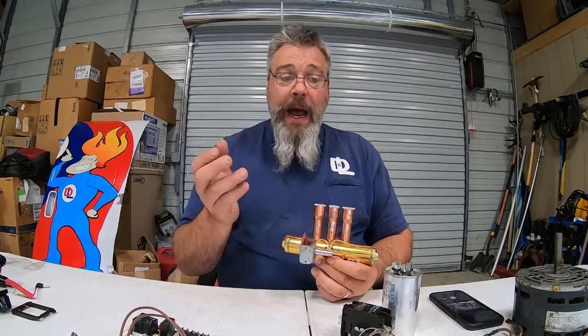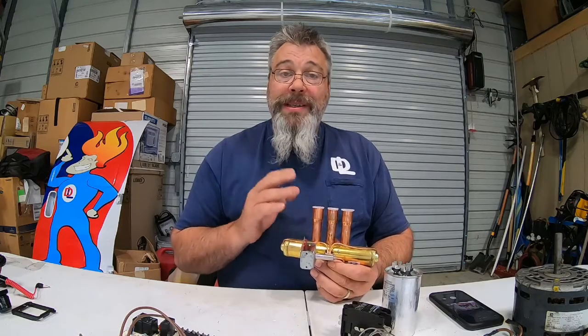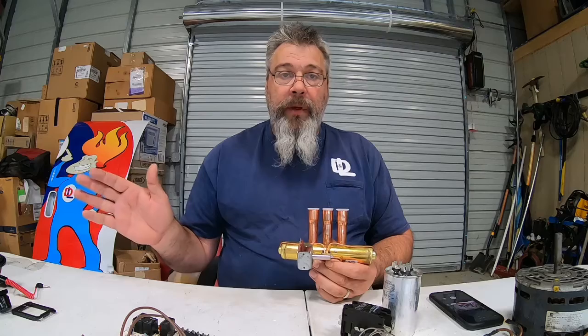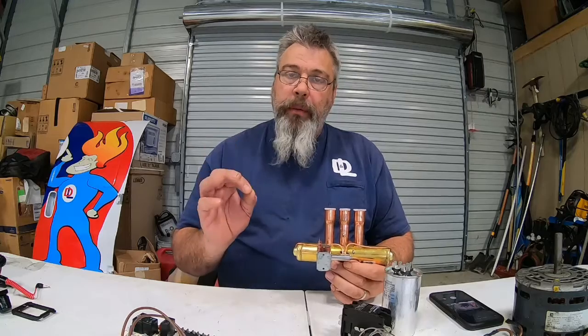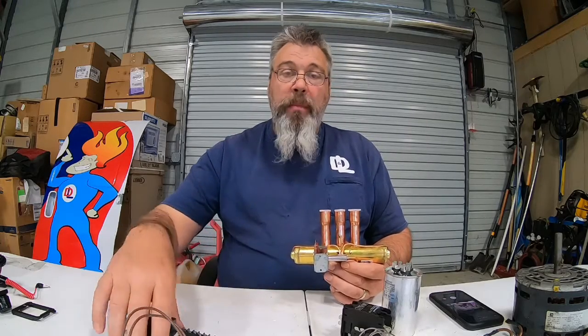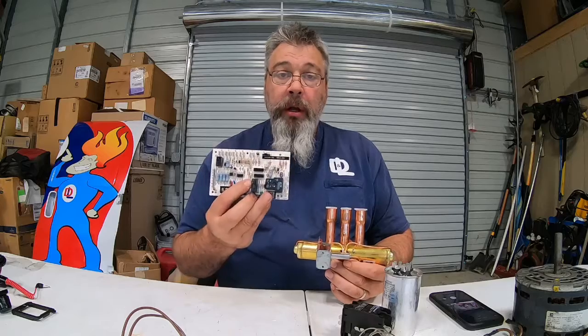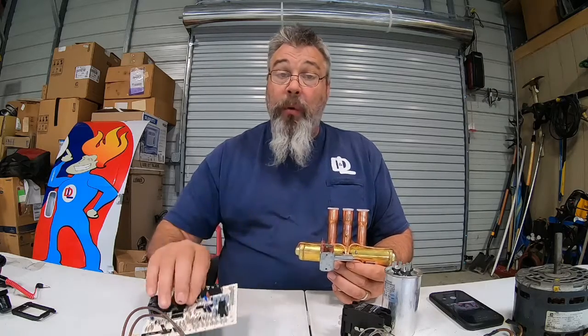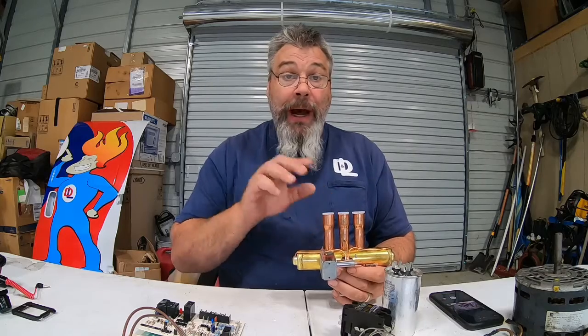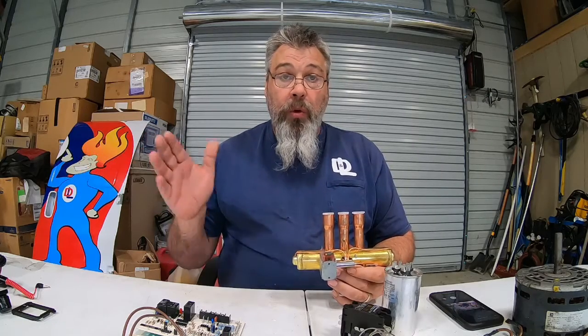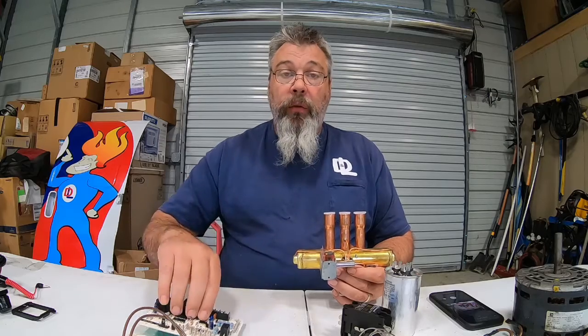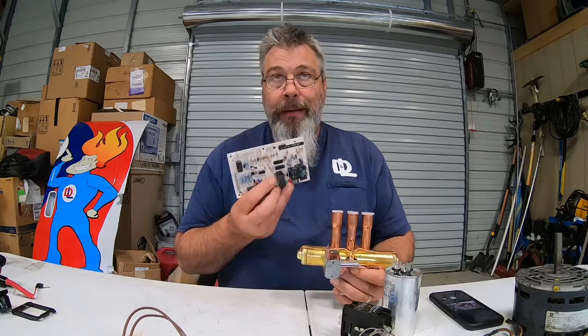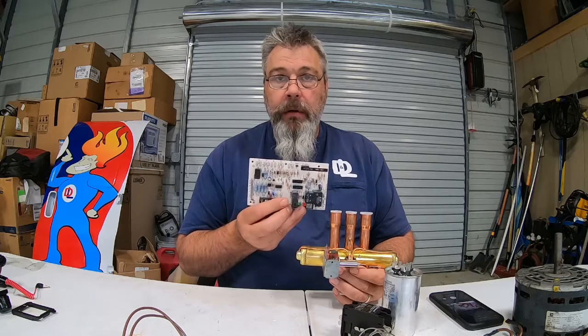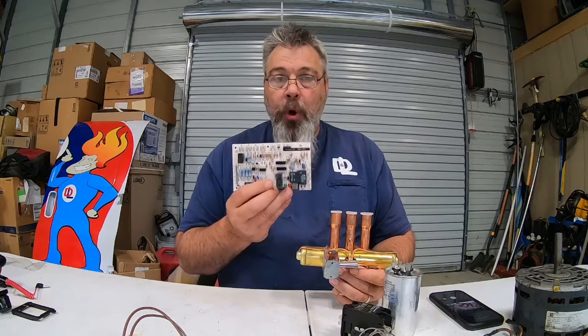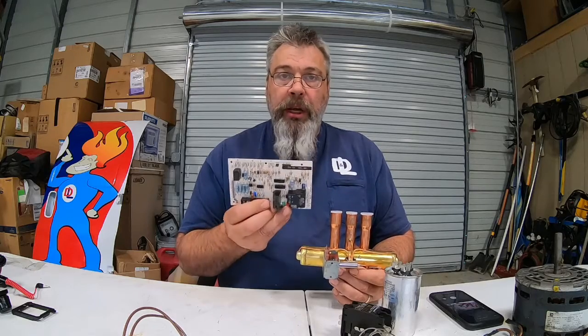Now, a couple of things happen in defrost mode. We stop the flow of refrigerant to the inside of the house. Well, you say, what happened? How do I get heat? Very simple. When that de-energizes, we go back to the control board that is now controlling what it's supposed to do, because now we only have refrigerant going to our condensing coil, not to the inside of the home. So we then initiate what we call secondary supplement heat. Supplement heat, in most cases here in Virginia, is electric strip heat.